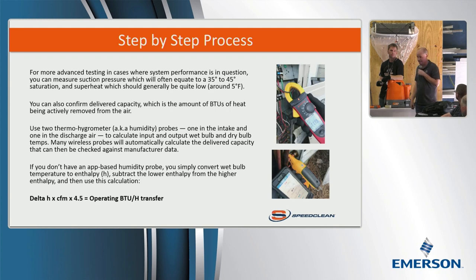Now, it's not always going to be the same, depending on load conditions, but it's going to be pretty close. You look at the chart, it's going to tell you what the capacity is. Keep in mind, the capacity is not always what you'd expect, just because it has an 18 in the model number doesn't mean it's going to always produce a ton and a half. That's not how it works. That's your nominal capacity.